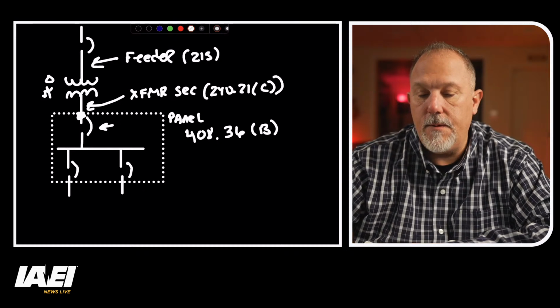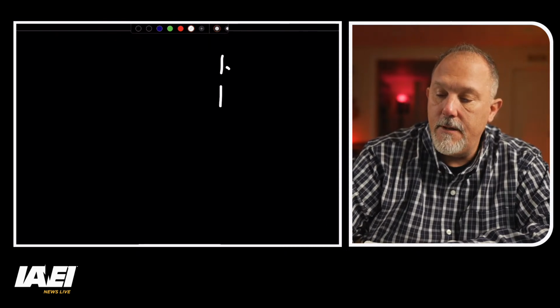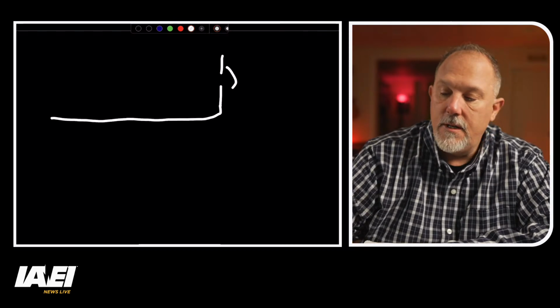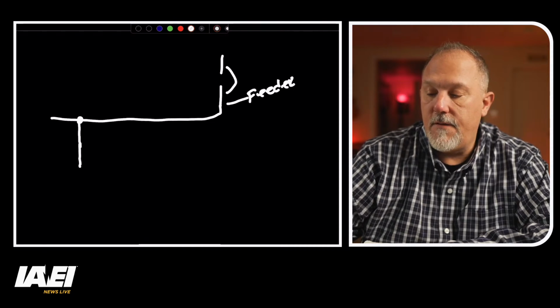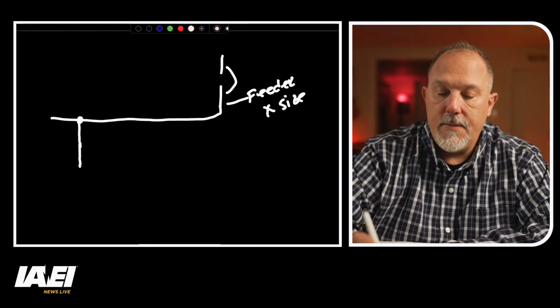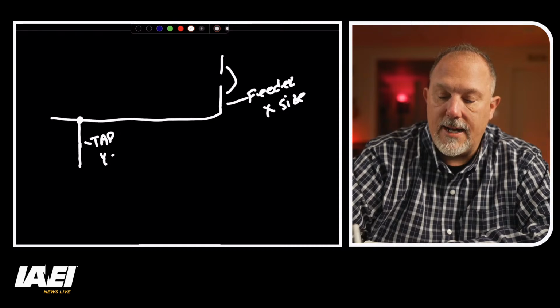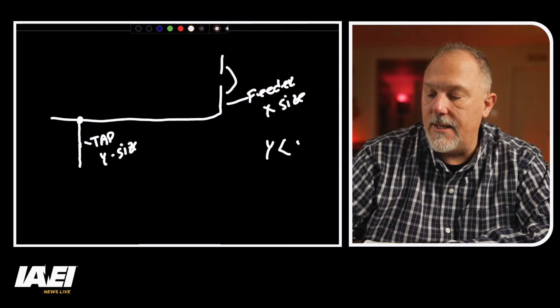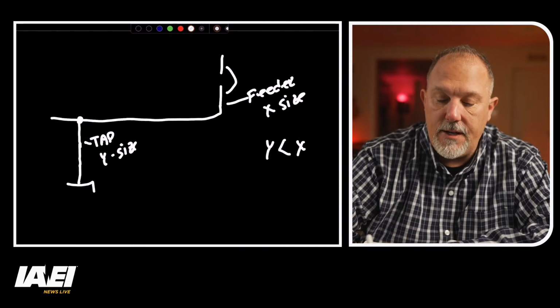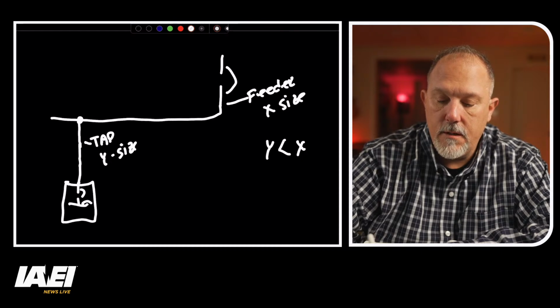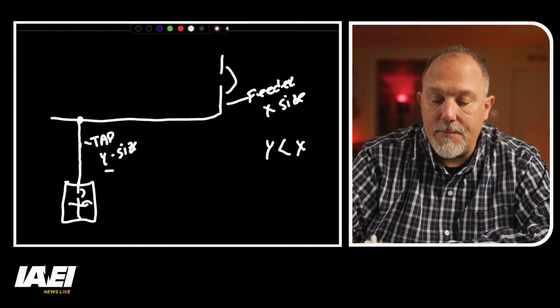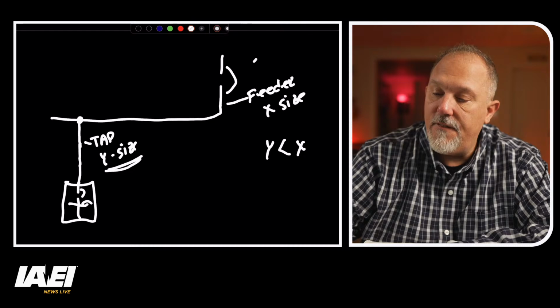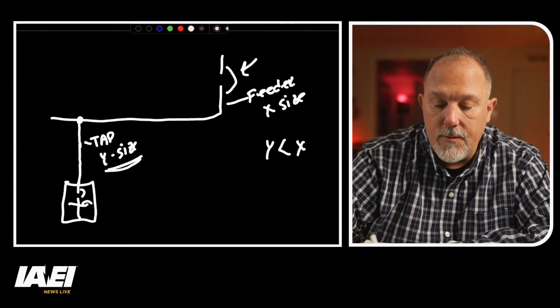All right, so the barrier would be placed in here. Now, the other condition is if I have a feeder tap. So let's say that I have this scenario, and I tap in, and I come down, and let's say that this is a feeder of, I don't know, X size, and this is a tap of Y size, and Y is less than X. Okay, so now I feed a panel board. So now I have a tap conductor that is of a smaller size. I have the breaker that is inflated in size. So I would require this to have a barrier.